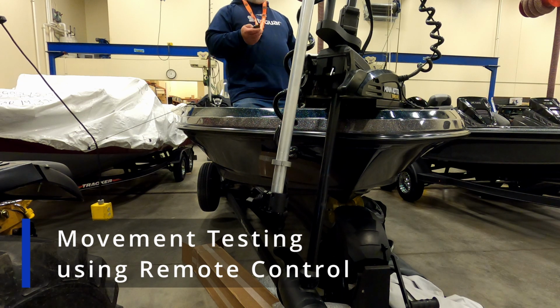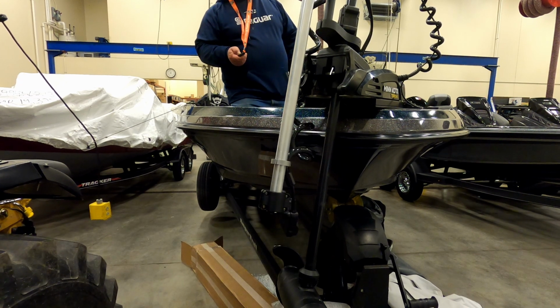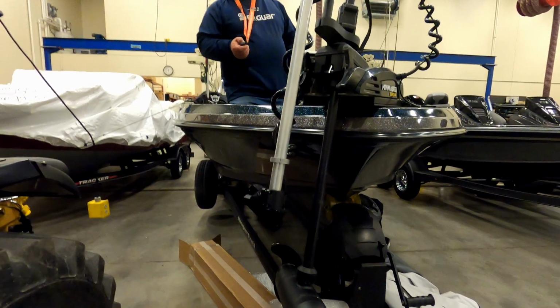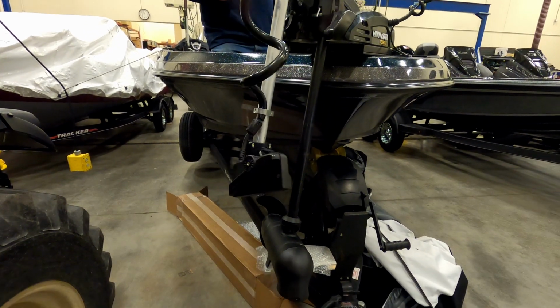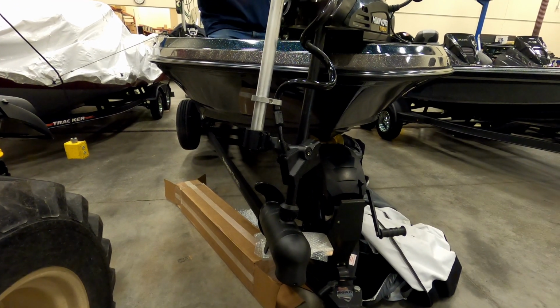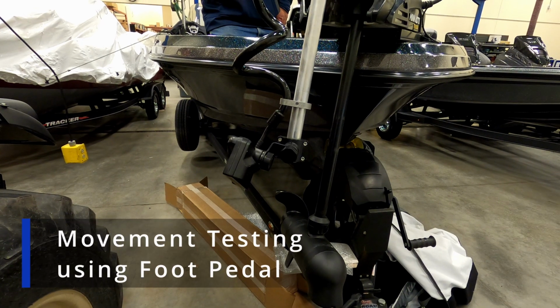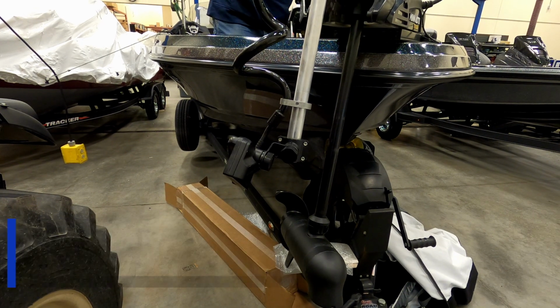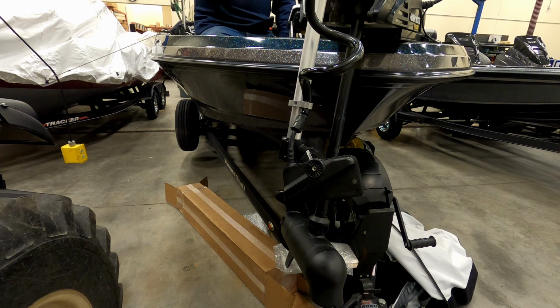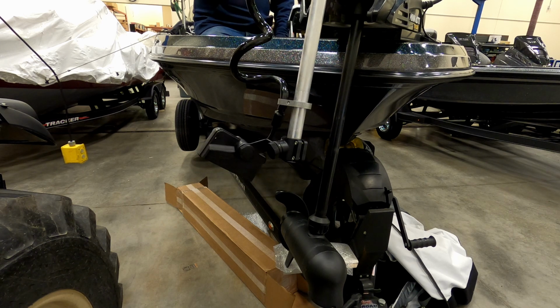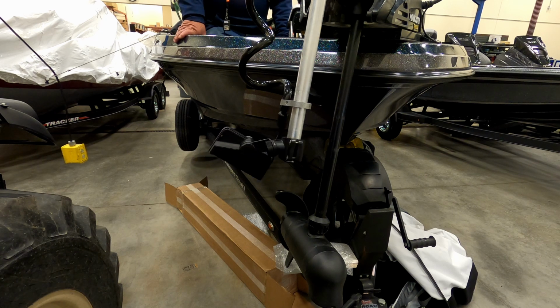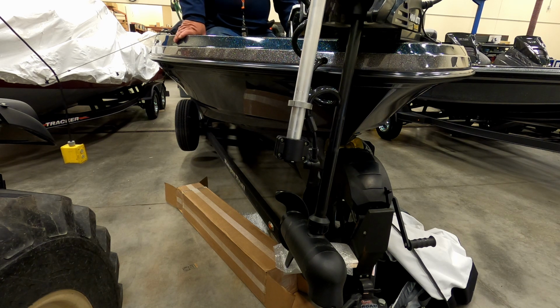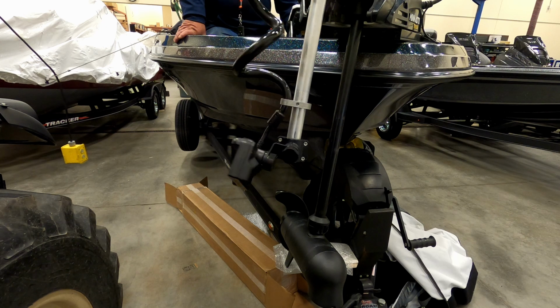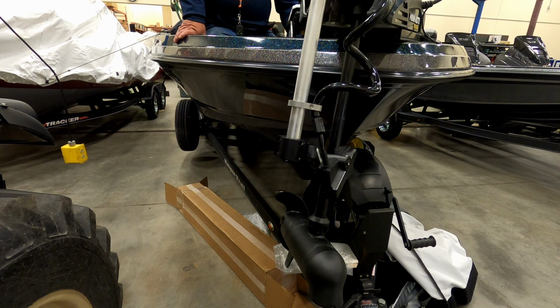So what we're doing now is checking the movement tests, making sure everything clears and doesn't hit the pole or anything else. We were hitting the pole earlier, before we did some adjustments to the brackets. Now we tested it with the remote control, then we retested it with the foot pedal. Again, you need to test with both and make sure both units are working properly and hitting the limits. That's what we're doing now, making sure it hits the two end limits.